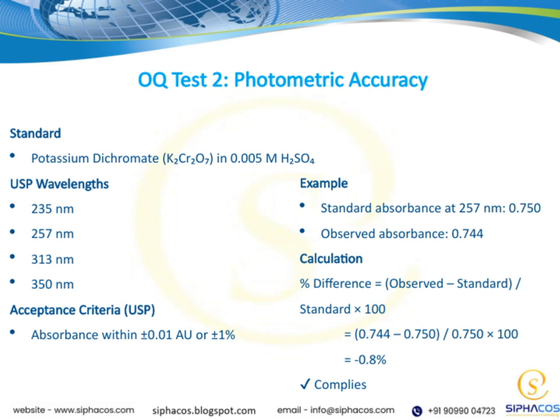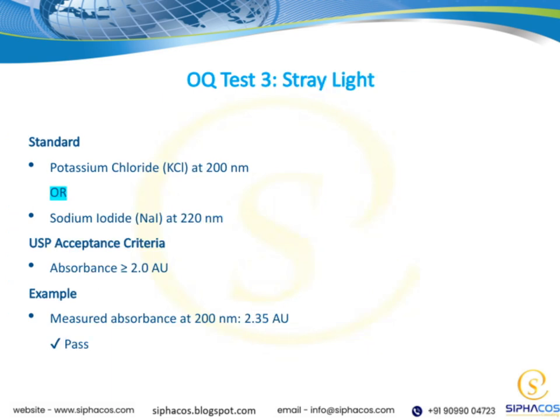All right, now let's talk about OQ Test 3, which focuses on stray light. When we're checking this, we have two standard options. One is potassium chloride, or KCl, which we test at 200 nanometers. The other is sodium iodide, NaI, tested at 220 nanometers. The key here is the acceptance criteria established by USP, which is that the absorbance should be 2 or higher. That means, if we measure an absorbance at the specified wavelength, and it's at least 2, we pass the test.